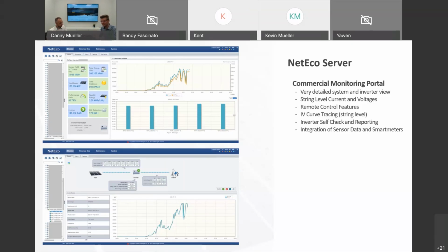And what you get at the end of that test is a PDF document, which shows you the inverters which might have some issues, for example, high AC voltage. And all the other ones are also listed, but they are not in focus. So with that feature, you really have that clear focus on what are the devices and your assets in the system or in your portfolio which have some issues, and which are the ones you don't really have to look into because they're operating normally. In the system, you can also implement a multitude of different environmental sensors or smart meters. We typically use the AcuRev from Accuenergy as a very popular tool, and that can be used for zero feeding applications or feeding controls, for closed loop reactive power control, and all kinds of smart applications when you're not only having a grid-tied solar system.